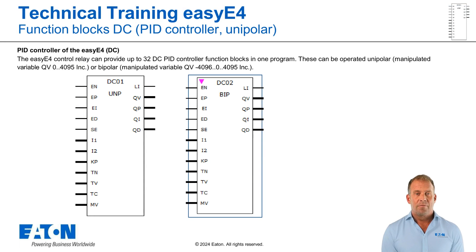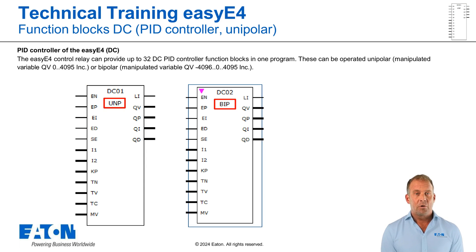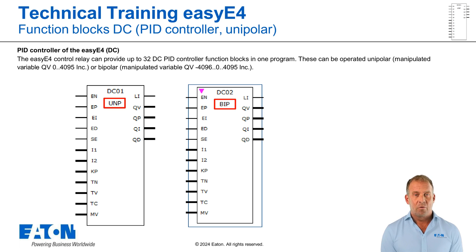The easyE4 can provide up to 32 DC PID controller modules in one program. You can choose between unipolar or bipolar operating mode in the parameters for the function blocks. In the unipolar operating mode, a manipulated variable of 0 to 4095 increments is provided. In the bipolar mode, a manipulated variable of minus 4096 to plus 4095 increments is provided.